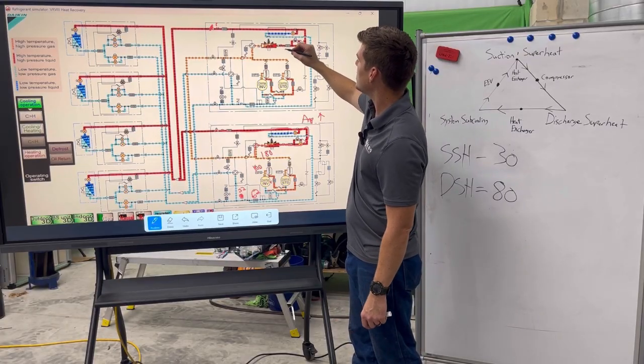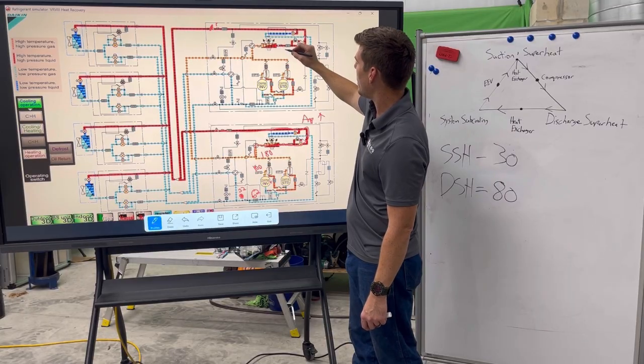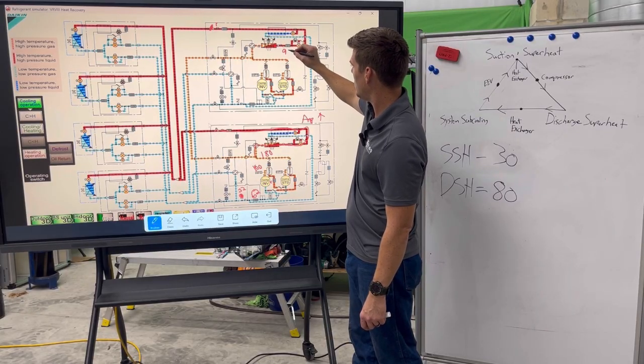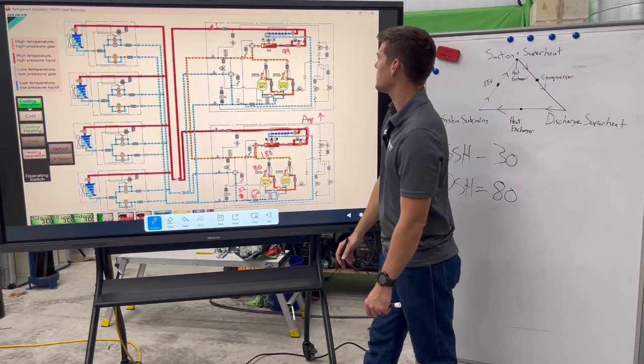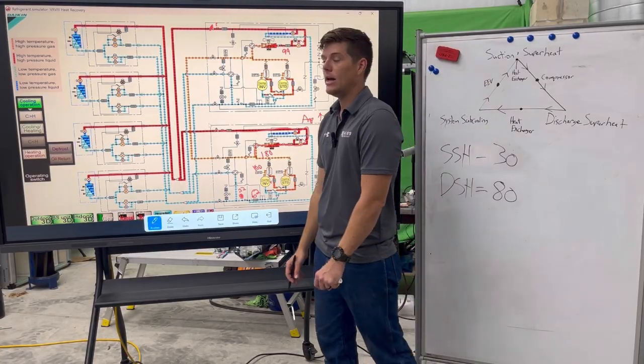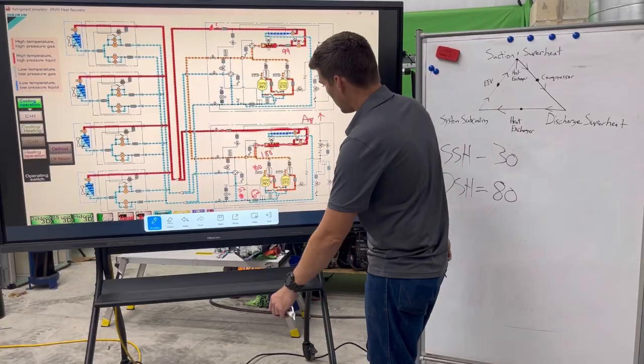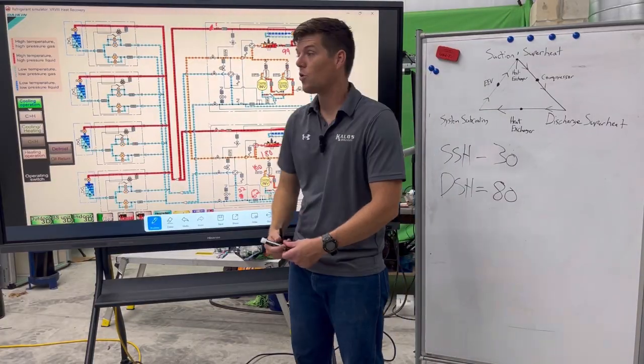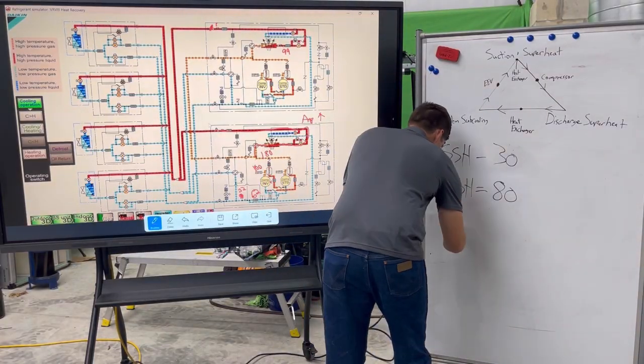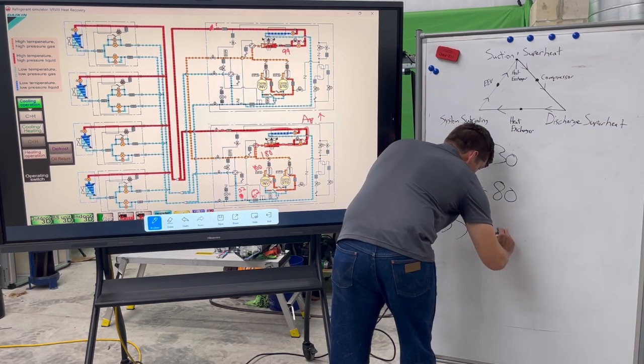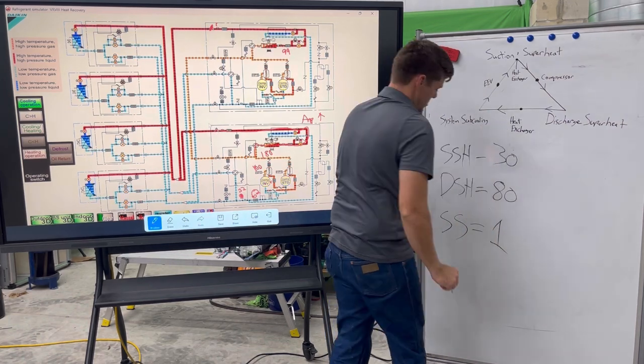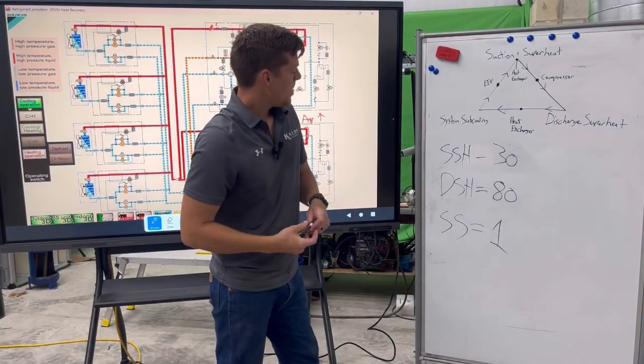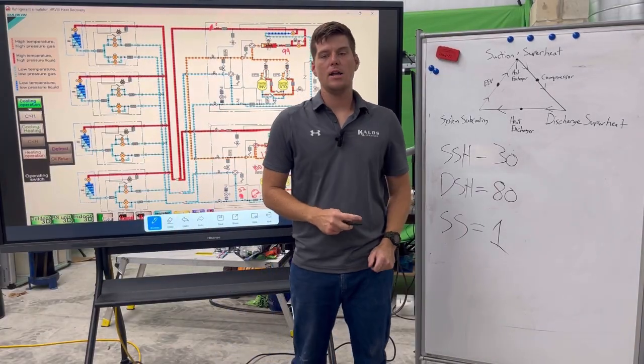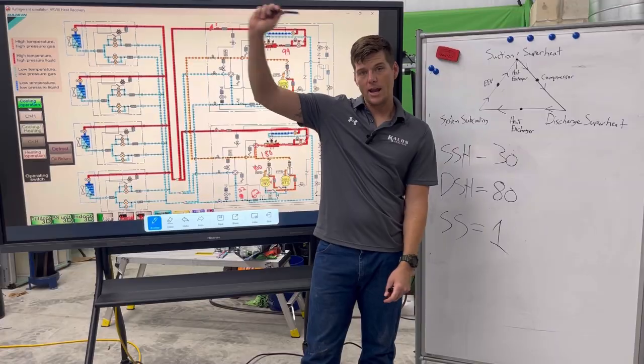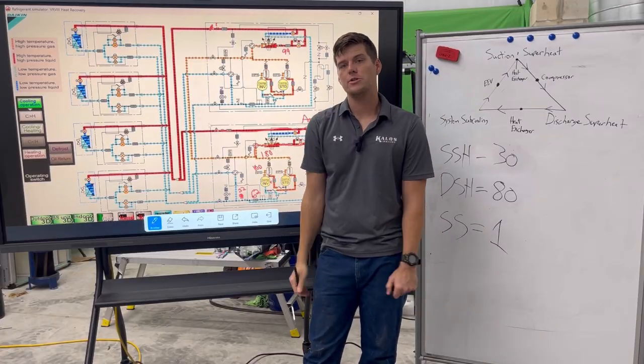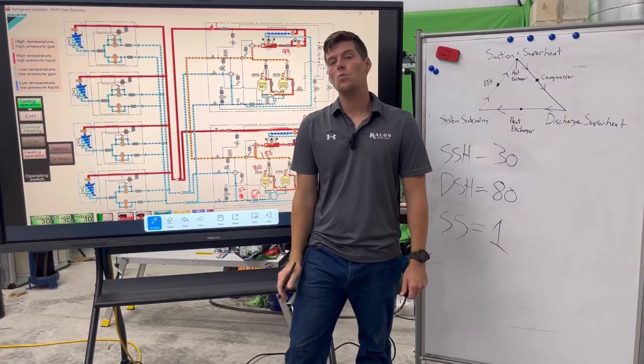And so for here, what do we have? Well, we have a 99-degree liquid temp. And what does that tell me, 99-degree liquid temp? Well, I take 99 minus my 100-degree saturation temperature, and what do I get? I get a beautiful number 1. Now, when I say system subcooling, I am not saying that you can hang your cowboy hat up on this diagnosis and you're done, charge the customer and tell them their system's undercharged. No, it doesn't work like that.